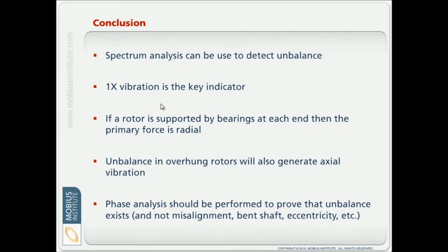So even though you may be looking at a fan and you say well it's most likely to be unbalanced versus eccentricity or bent shaft or some other sort of fault that generates 1x vibration, phase can help us ensure that it's unbalanced not something else, and we can then figure out how to do the balance job.